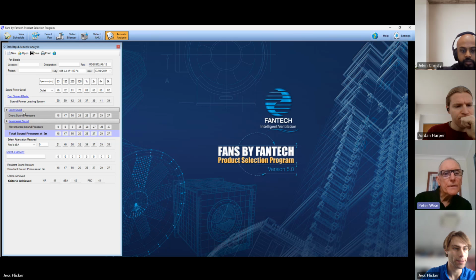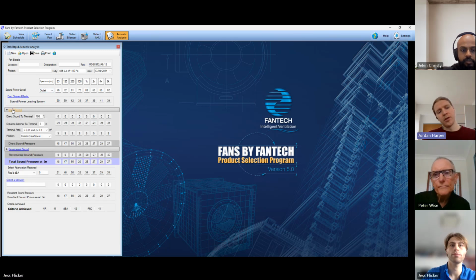Yeah. So just go back. You've got sound power level at the top here. Sound power leaving the system, direct sound pressure. Between the sound power leaving the system and direct sound pressure, there's a spectrum of correction factors to convert from sound power level to sound pressure level, which aren't shown there. But they are shown on the other spreadsheet. But anyway, keep going. Isn't it there at the bottom? It says the sound pressure.